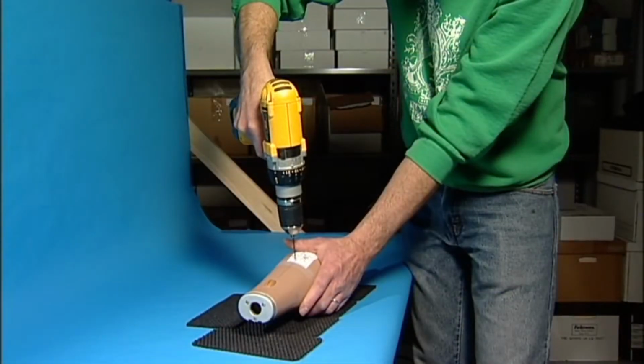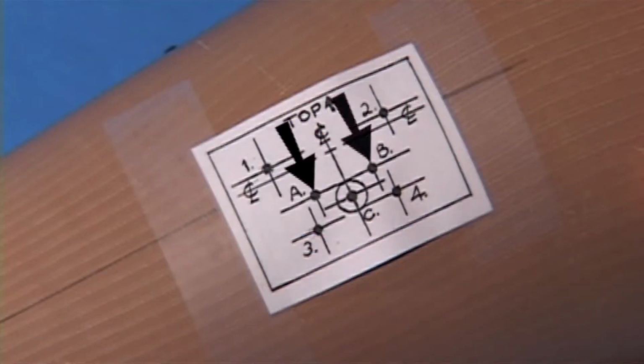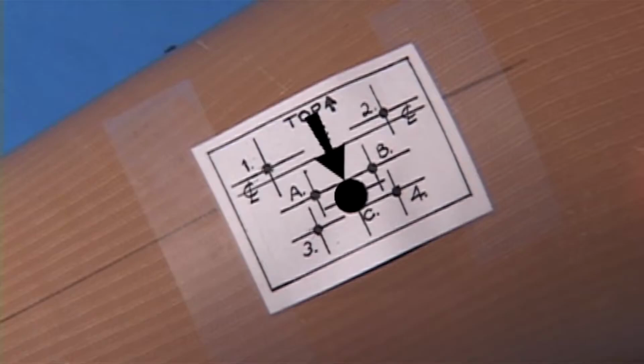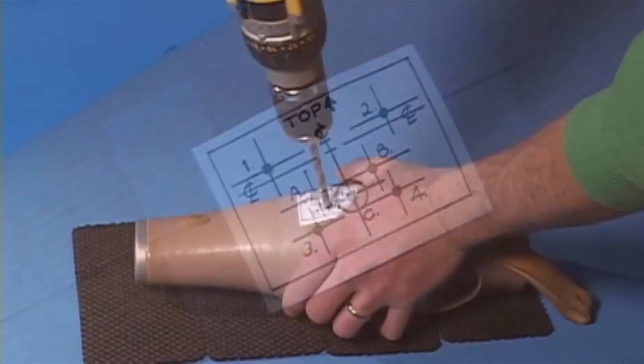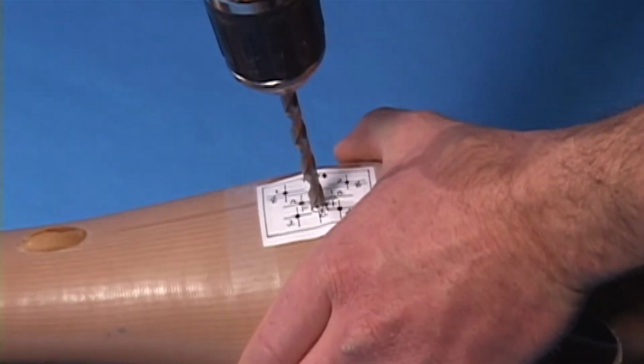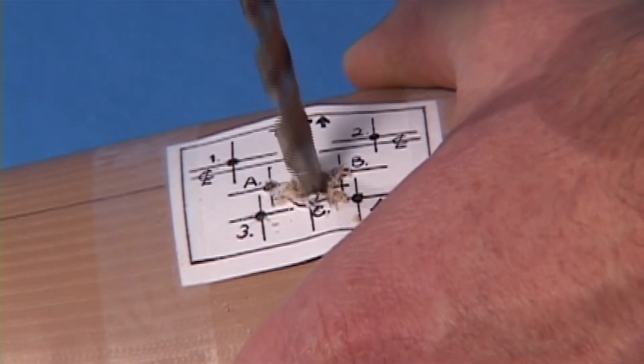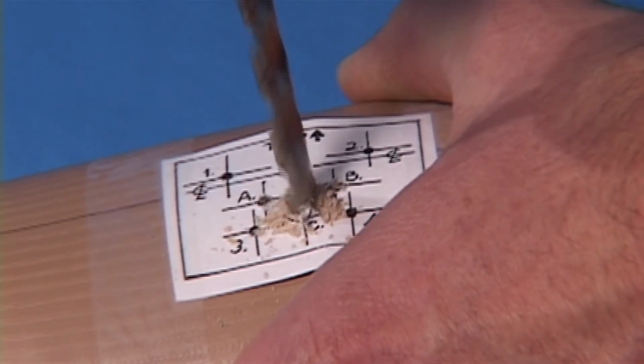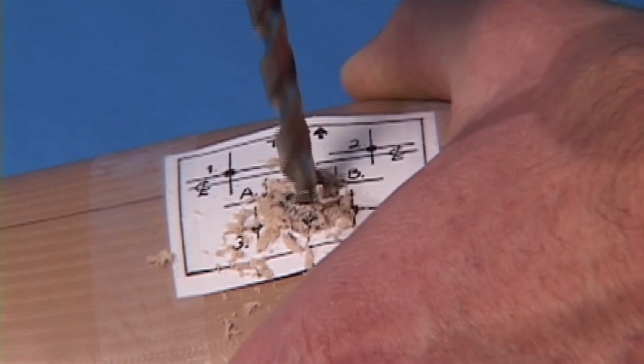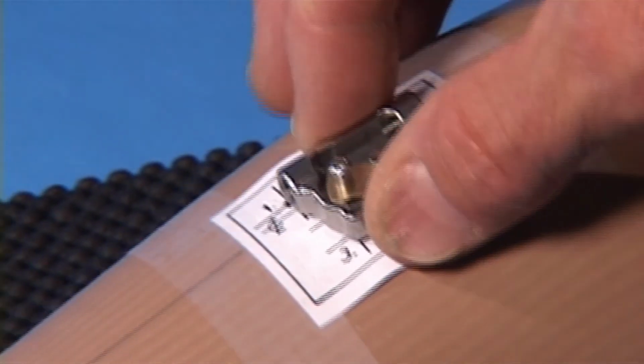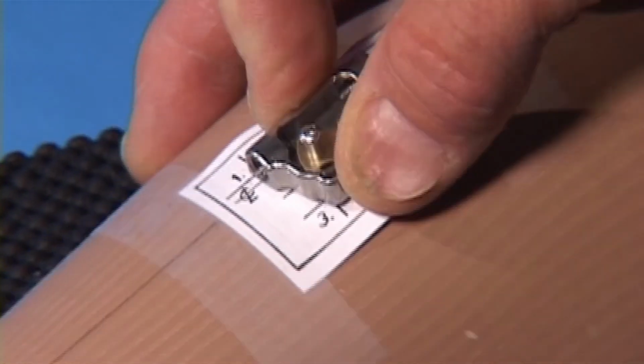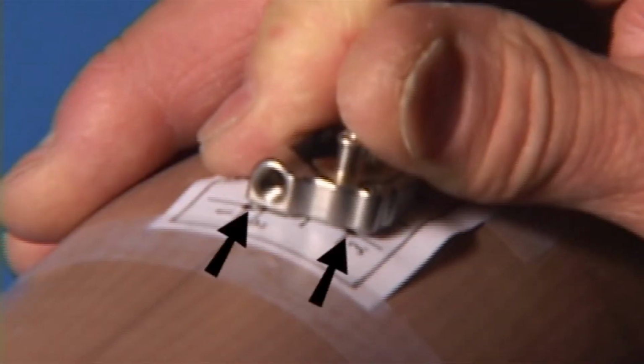Drill 5/64 inch diameter holes at the locations marked A, B, and C. Enlarge only hole C to 1/4 inch in diameter to accept the boss on the bottom of the structural base. Carefully drill this hole 5/32 to 1/4 of an inch deep through the prosthesis laminate shell. This boss transfers mechanical forces to the prosthesis shell instead of the mounting screws. Place the structural base over the template. The boss should fit into hole C, and the 4 small feet on the bottom should touch the prosthesis' surface, matching the hole marks on the template. The structural base should sit on the prosthesis, stable and unable to rock.